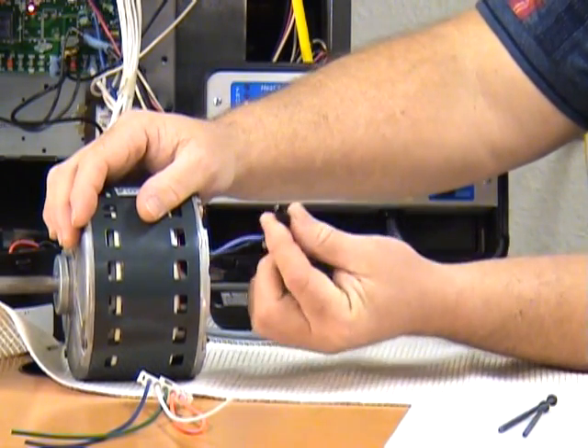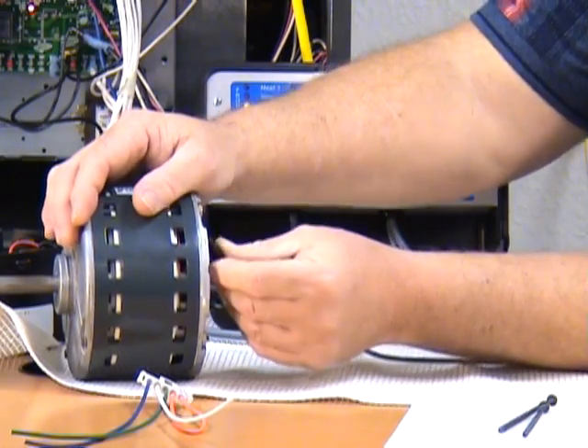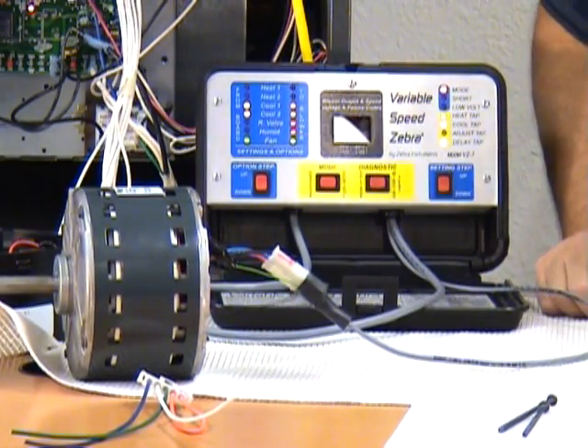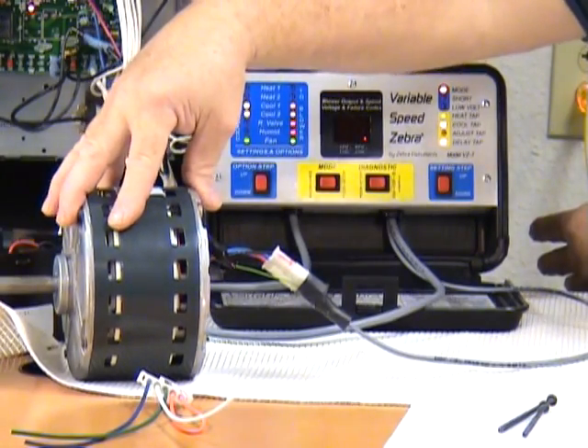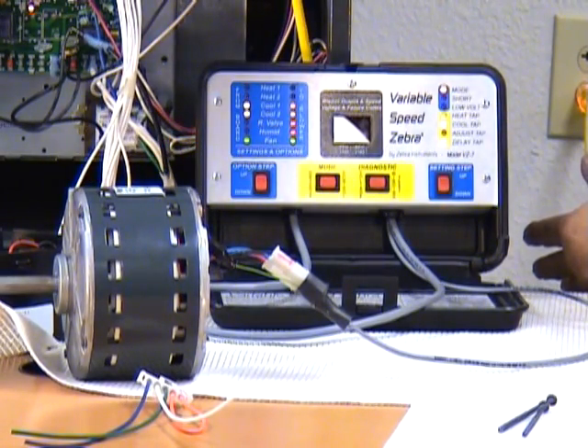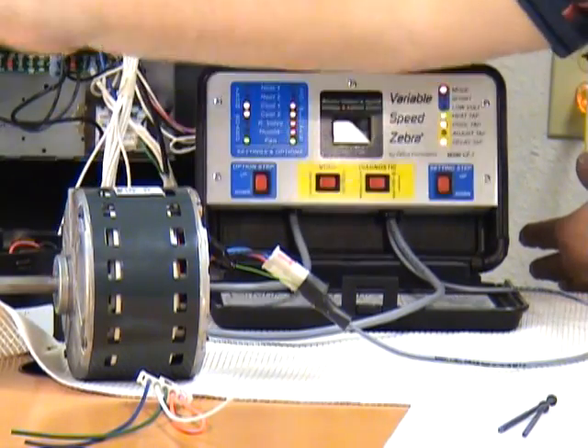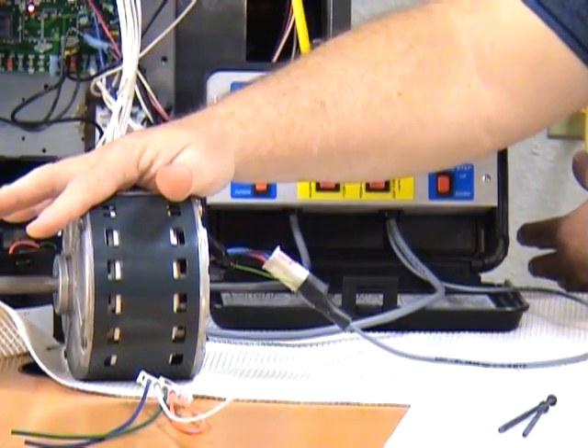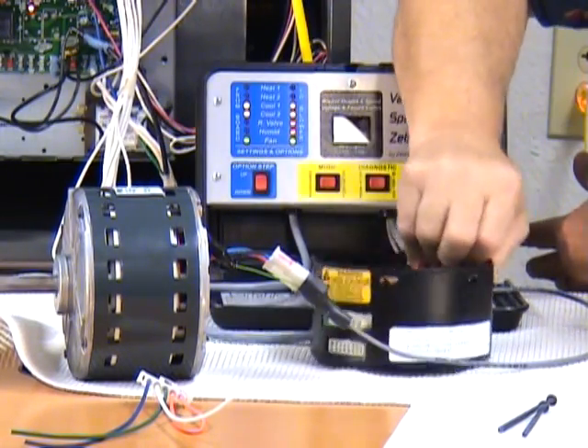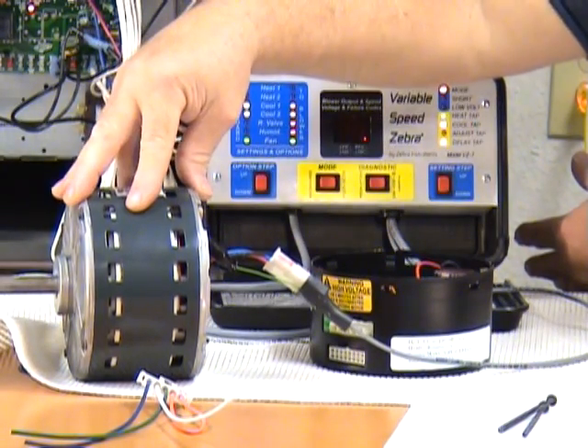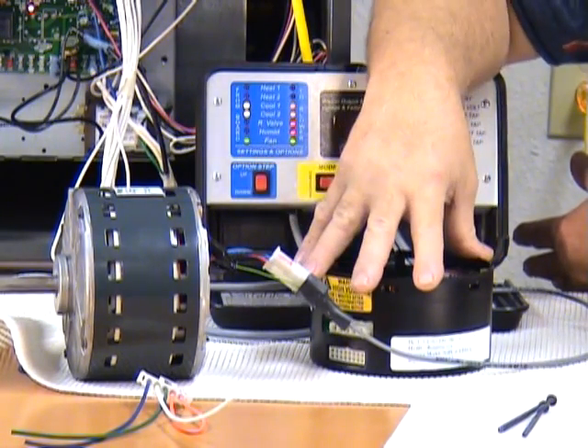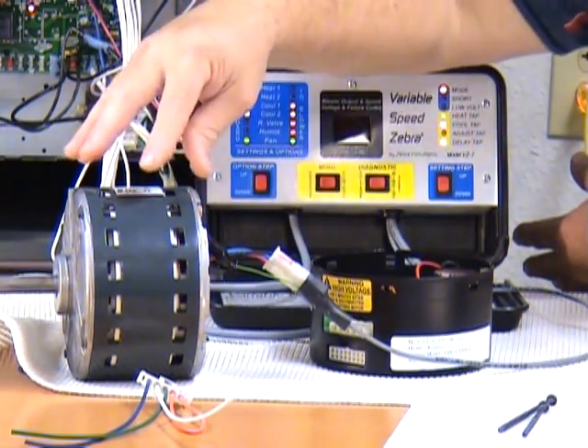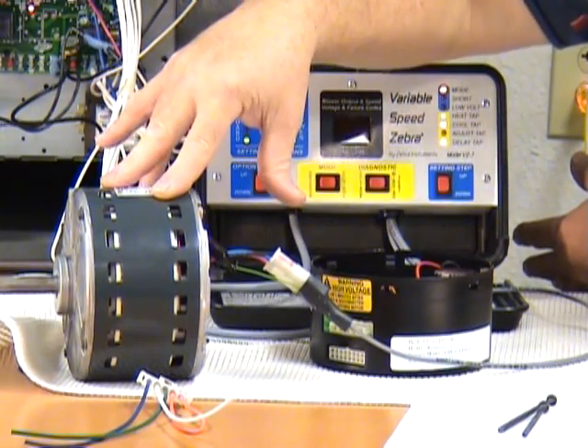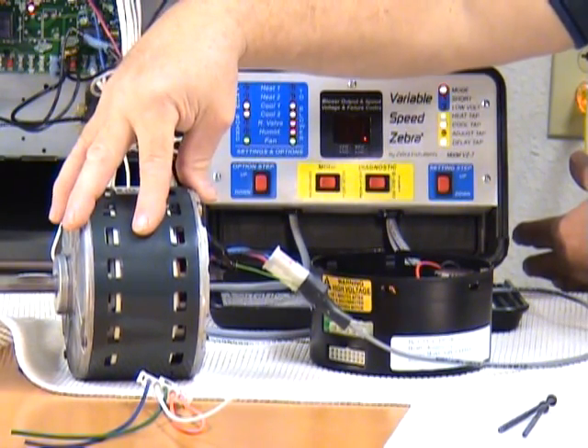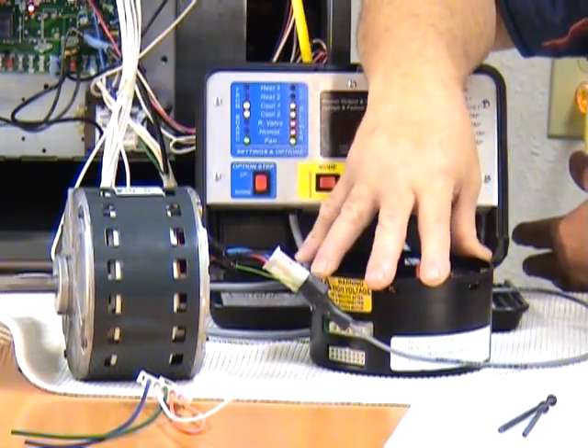The alligator clip that's on this harness needs to be attached to the motor. To do this test properly, you really need to have the motor out of the furnace. I know that's a lot of work, but you're going to have to take the motor out anyway, because you're either going to replace this section or you're going to replace the whole motor. You can't see this section. You're either going to replace the electronics section or you're going to replace the whole motor. There's no easy way to test the electronics section directly, so if you know the fault is in one of these 2 pieces, you can determine if there's a fault in here, and if the fault is not in here, therefore it has to be in here.